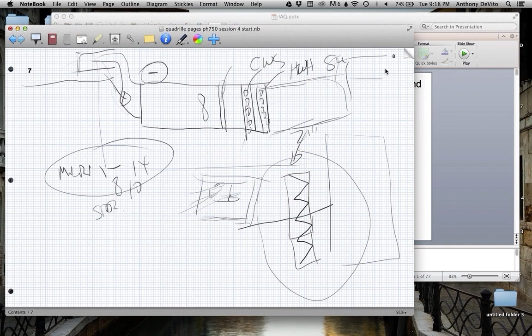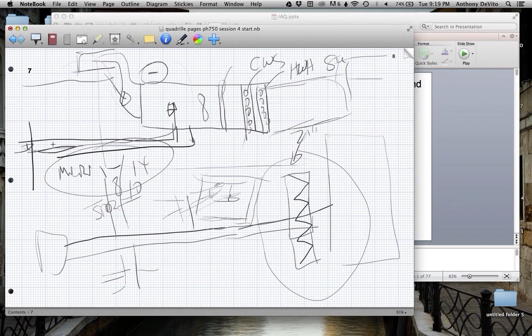Okay, now on the suction side of this, we're under a negative pressure. So if I take a small duct, connect it here, and run it to an outside wall, what happens to the fresh air on the outside of that? It gets pulled in here. That's your fresh air intake. And what they'll very frequently do is put a damper, a device to control the flow, and that might be motorized so that you can control the percentage of air that comes in through here. And what's pulling the air in? It doesn't have its own fan. What's pulling the air in is the negative pressure on the suction side of that fan on the air handler.